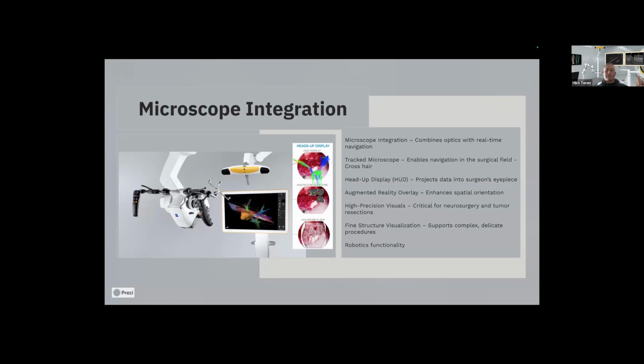But remember now, here we've used the head of the microscope as a pointer, but we still need to see the image that's on the navigation screen. So the surgeon, again, doesn't want to look away. So what do we do? We have now, as we see more and more of these scopes coming out, head-up display systems built into the microscope. So you can see there we can actually place a picture-in-picture into the ocular so that the surgeon can see what he just looked at with his crosshair correlates to these three intersecting, as we saw earlier, axial, coronal, sagittal images on the preoperative scan, and now he knows what he's looking at, and he can continue on as if it was an electronic pointer.